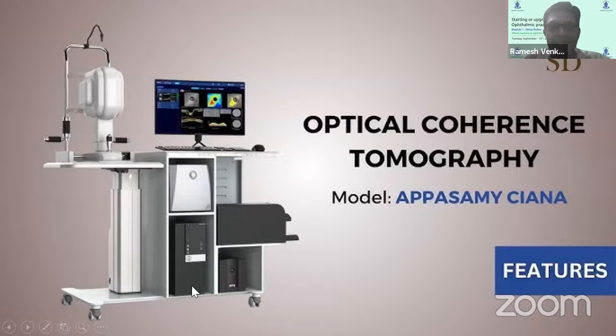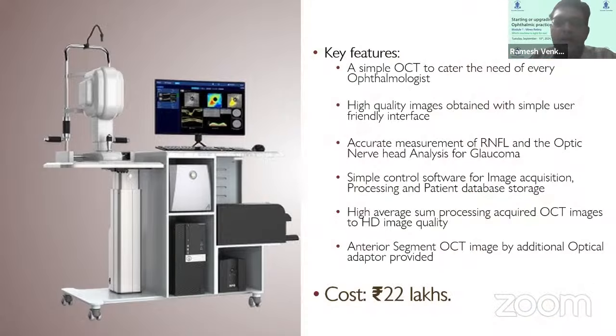Now, let's look at the indigenous ones we have as well. This is the Appasamy Ciana, which is our indigenous make. It's a simple OCT machine which caters to the needs of all ophthalmologists. It provides high quality images and an extremely user-friendly interface. It provides both glaucoma analysis and nerve fiber analysis, and it has an excellent control software for image acquisition, processing, and a good patient database storage system. And when you have an additional optical adapter, you can also do anterior segment OCT imaging.